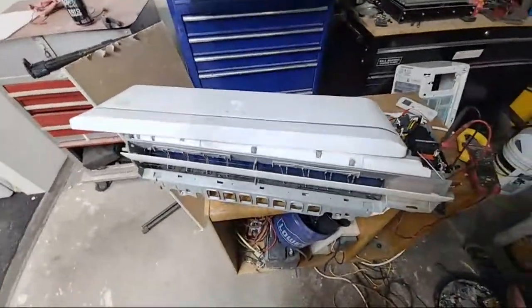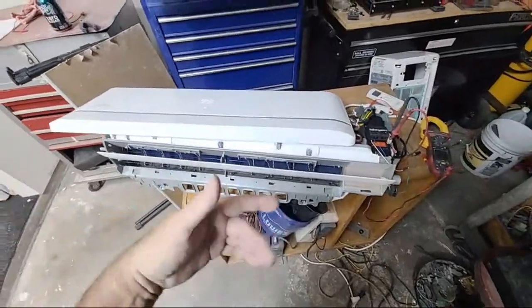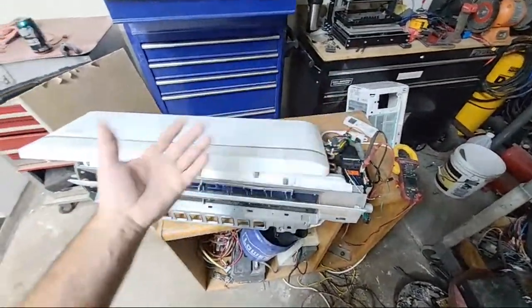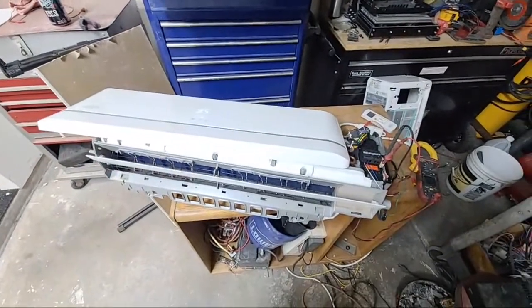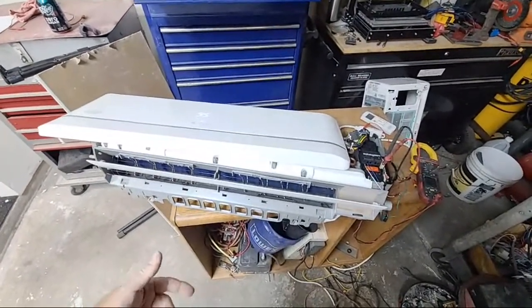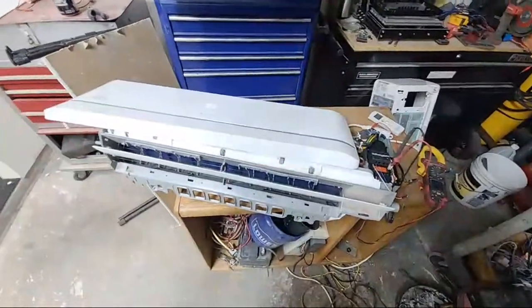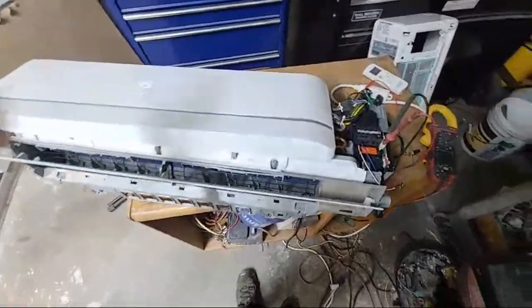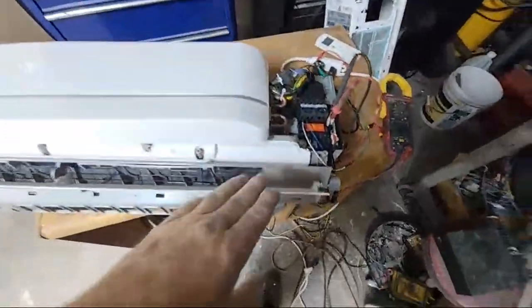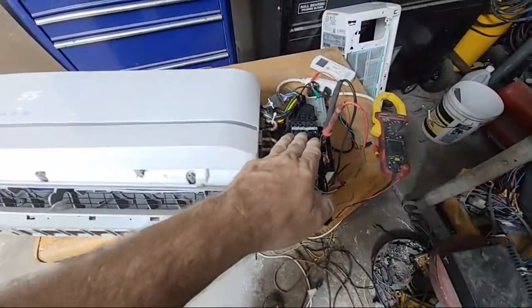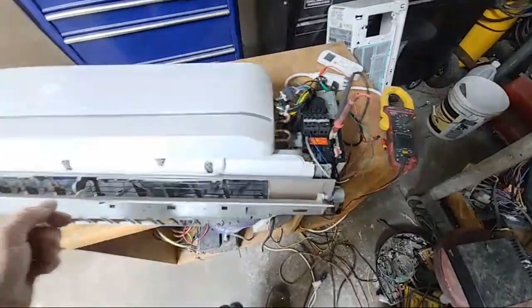I actually ran this for like a day and a half off the 120 volts and never got a fault, nothing. Now that just turned the fan only, not trying to set for cool or something, which it would eventually probably stop on a fault because it won't communicate with no outdoor unit talking to it between L2 and S. So I just have 115 volts, 120 basically, put into these two terminals right here.